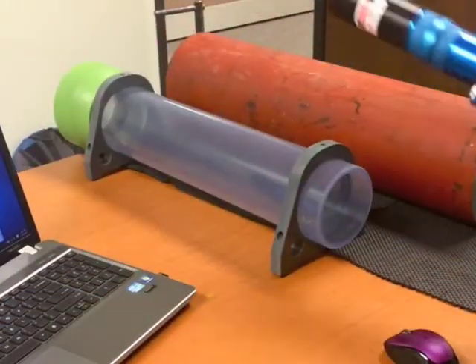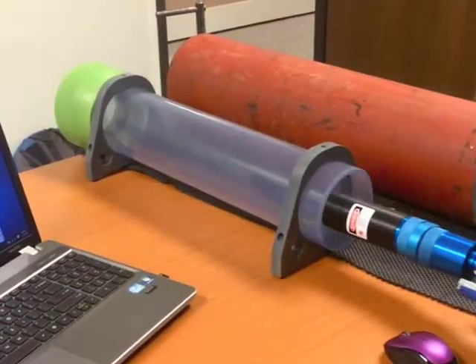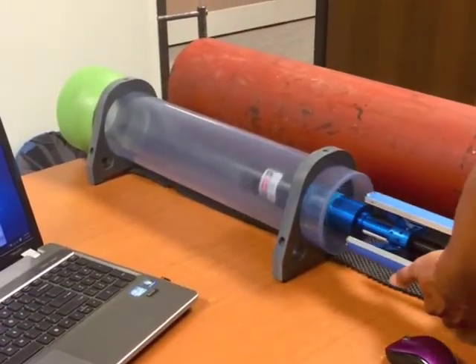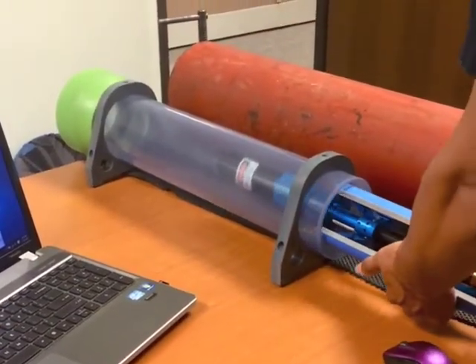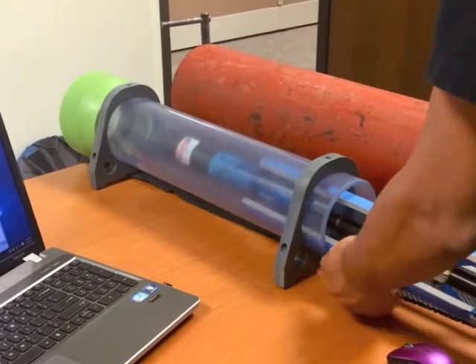The probe, now attached to the insertion rod and centering shoes, is inserted and aligned with the end of the tube.